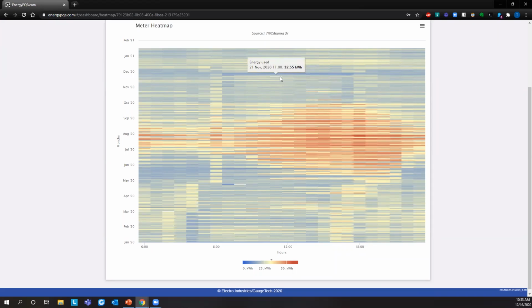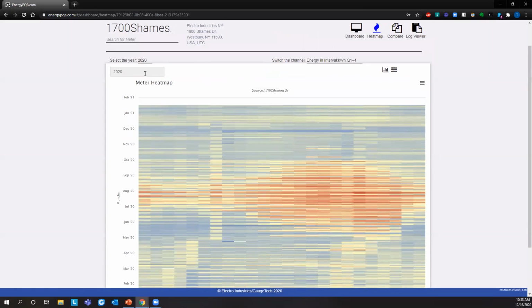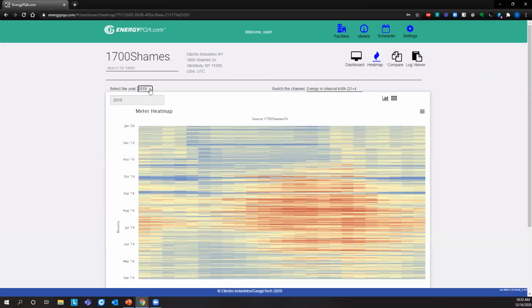In the winter, because we're on gas for heating, our usage is significantly lower because now we're not using electric for environmental control. So we can go back to 2019. Again, we can go back 4 years. This Energy PQA will keep track of energy information for the last 4 years. As long as your meter has logging information from the last 4 years, you can go back to the previous 4 years and look at your energy use throughout the year.